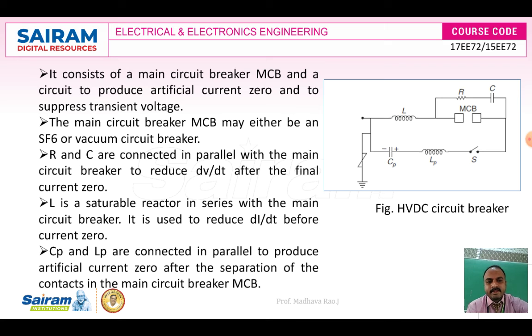And this is the HVDC circuit diagram. You can see it has an MCB. Across the MCB we have connected R and C, resistor and capacitor, in parallel. L is connected in series with the MCB, and Cp and Lp are connected on the secondary side of the MCB. Let us see why R and C are connected in parallel and L in series. It consists of the MCB, the main circuit breaker, and a circuit to produce artificial current zero, so that the current becomes zero. That is why the R and C are connected across the MCB.